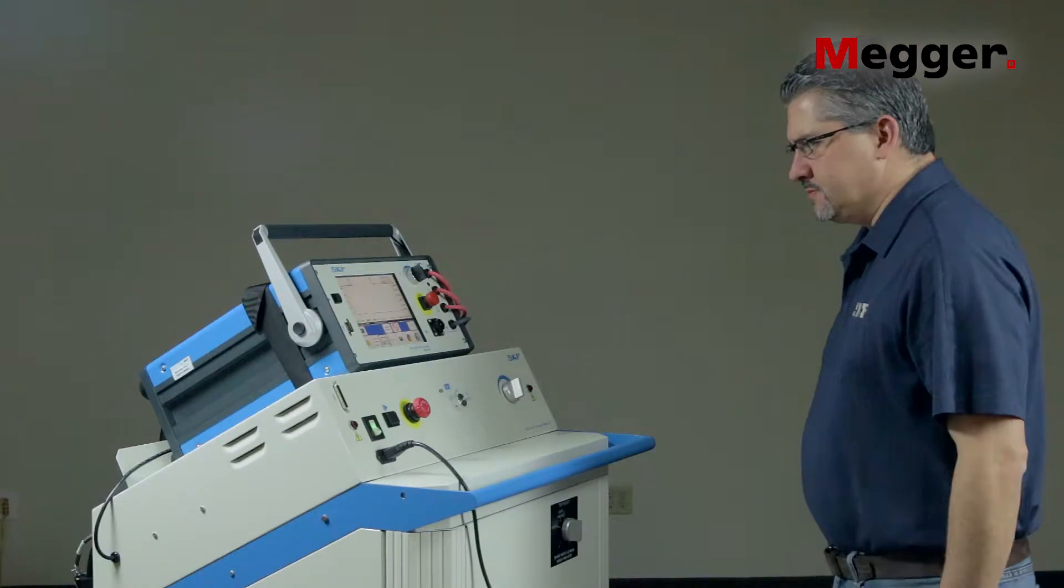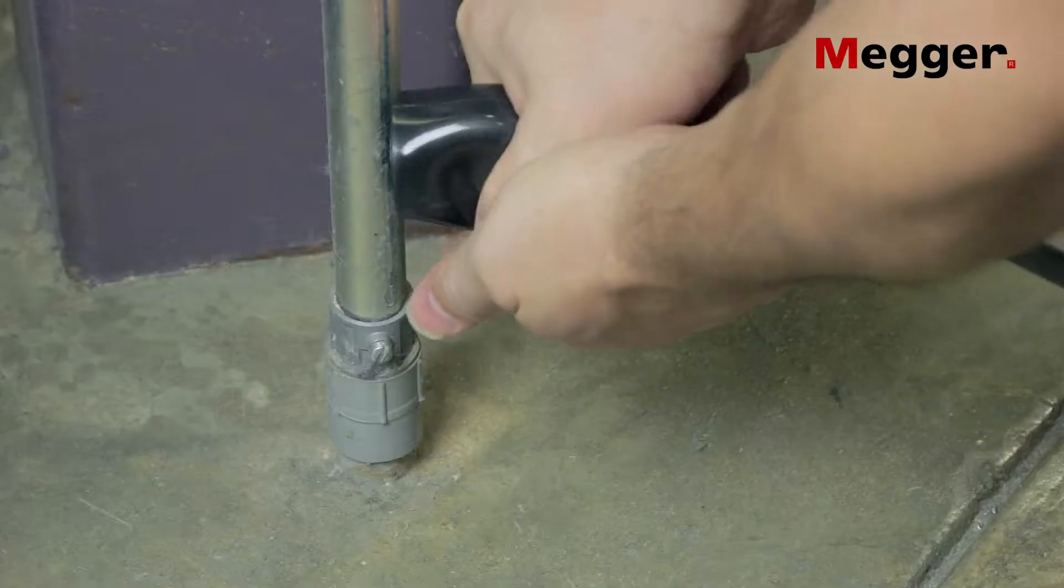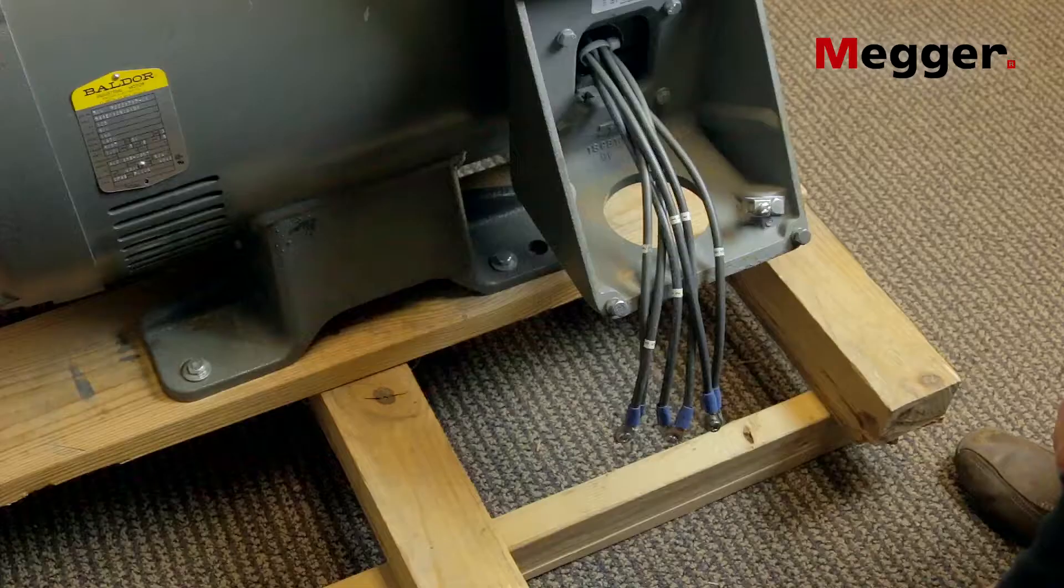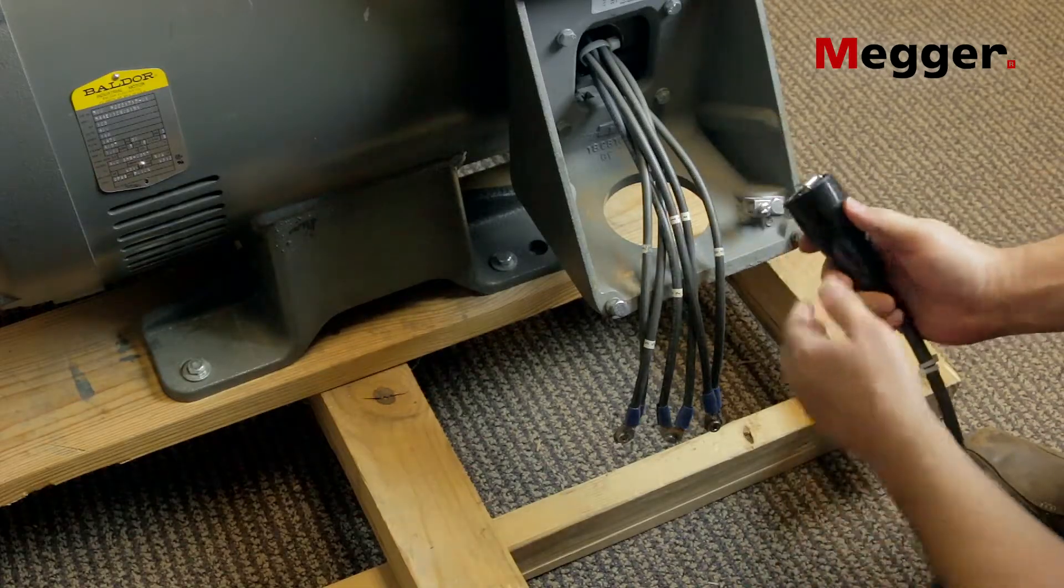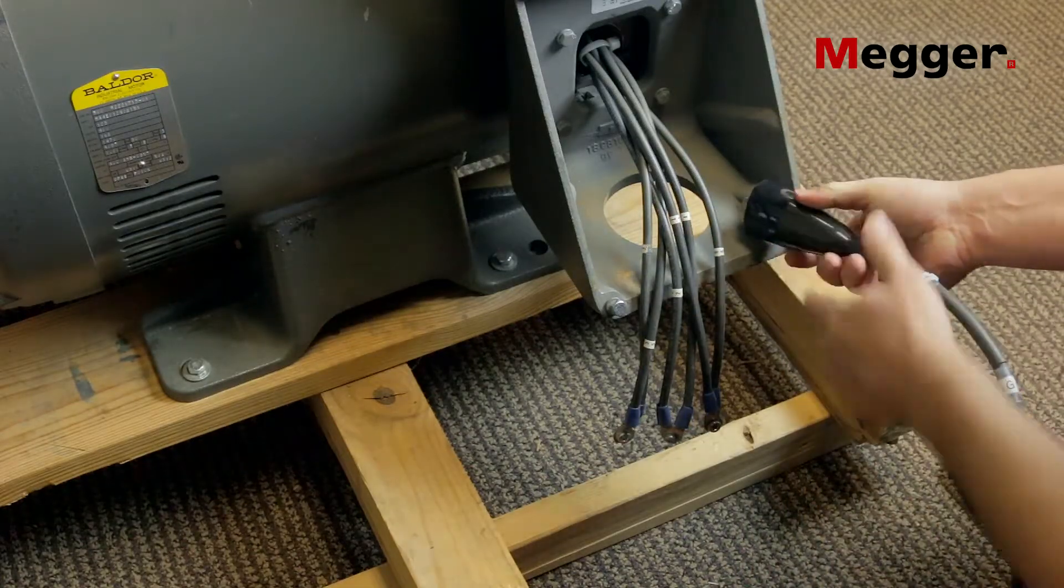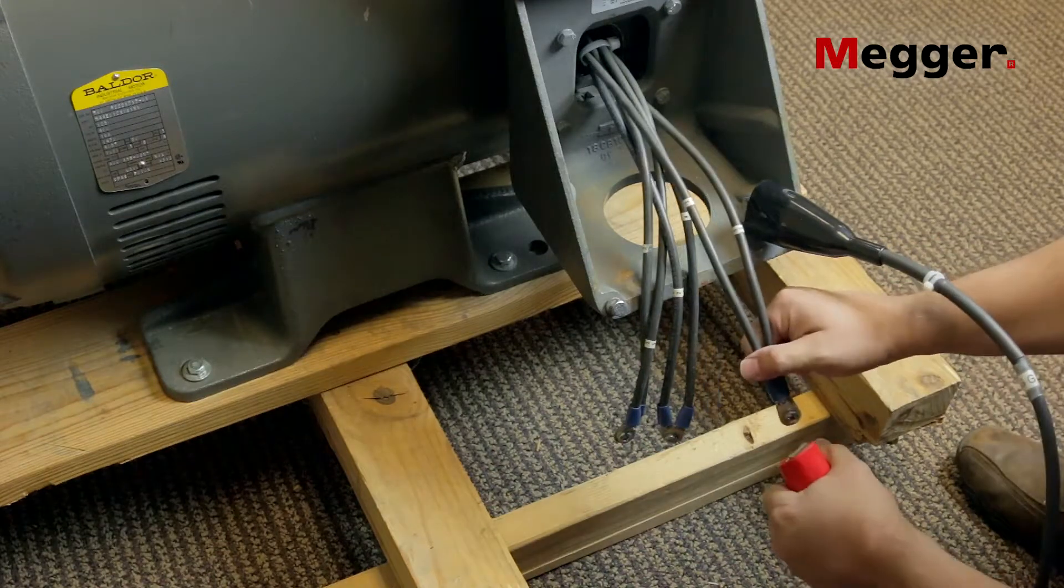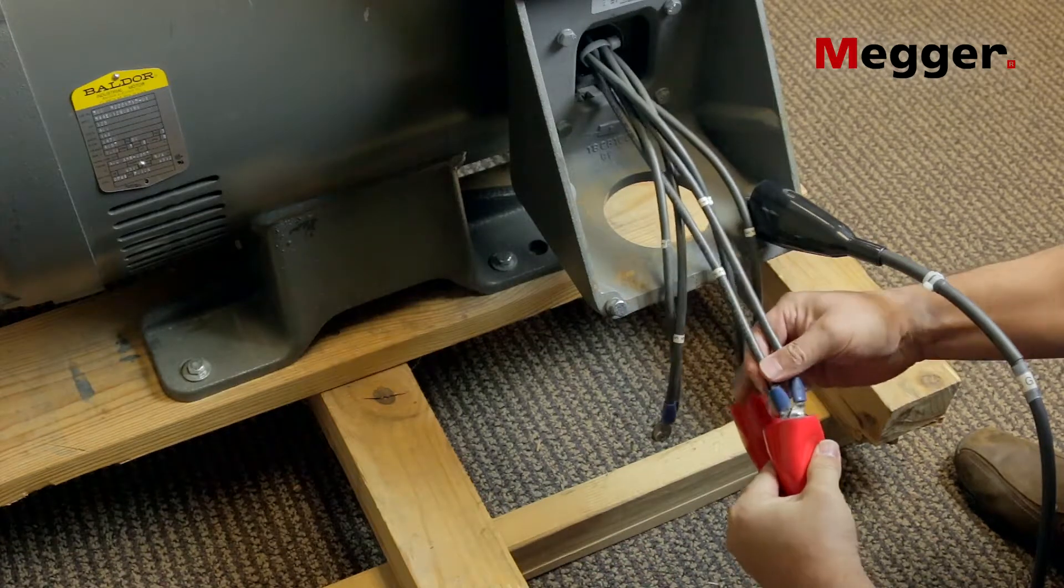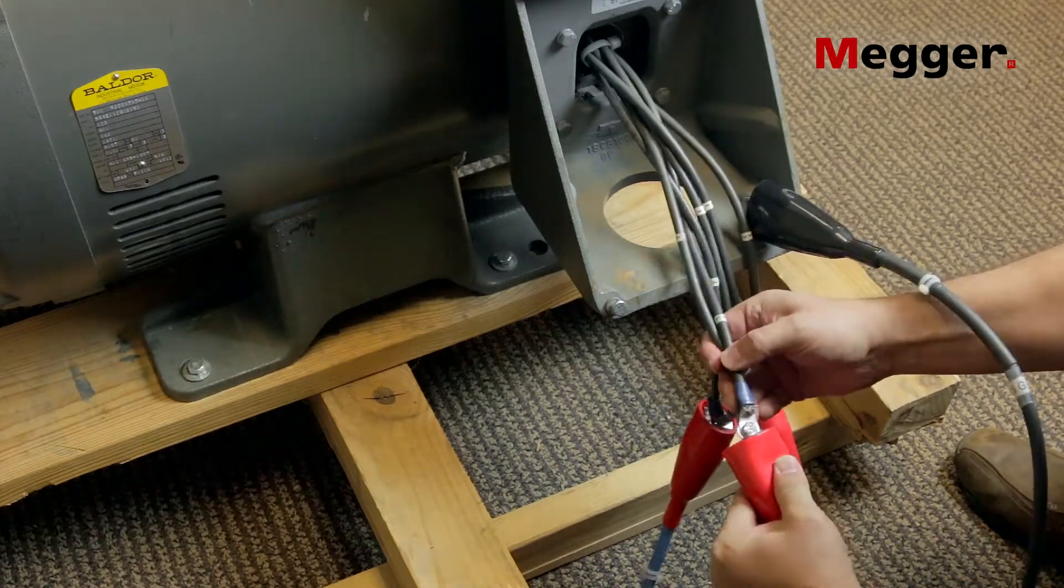This video assumes you have already connected the Baker DX to the power pack. Connect the braided ground cable to a known earth ground point. Connect the test leads to the motor stator terminals and the ground lead to a paint-free point on the motor's frame.